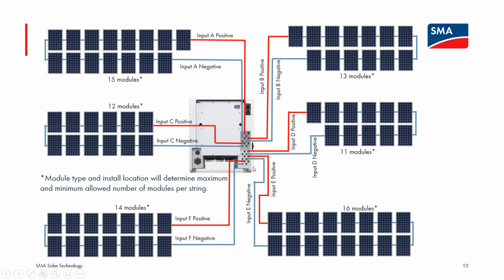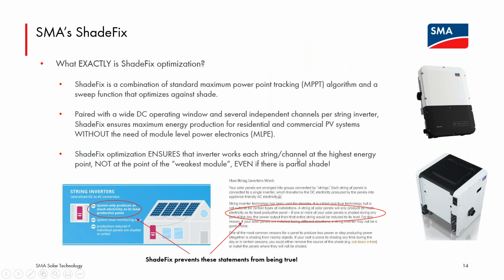With the flexibility, though, there is one design constraint so that we don't need that series fusing. You cannot parallel across the 6 tracking channel inputs. So a fully loaded CORE1 at a minimum is going to have 6 positive and negative home runs coming back to the inverter. I want to switch gears a little bit and talk about ShadeFix briefly. This is the energy optimization shade mitigating technology that is built into both our CORE1, and the image above that is our Sunny Boy residential single phase inverter. Both of these inverter lines have this ShadeFix optimization.